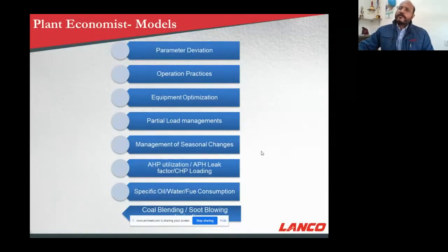In soot blowing also we have done some modeling, in the sense that no flux sensors are required. Based on the temperature profiles in the flue gas path, steam temperature and flue gas temperature, the heat absorptions are calculated, and based on that heat absorption we have calculated a cleanliness factor, where the maximum heat absorption, considered as one, is immediately after AOH in the stabilized condition, annual overhaul. Based on that certain triggers are made. This will help in doing the smart soot blowing optimization. It's a very simple technique, but we can use this. We can see the cleanliness factor coming down and we can act. So optimum soot blowing frequency can be decided based on that.